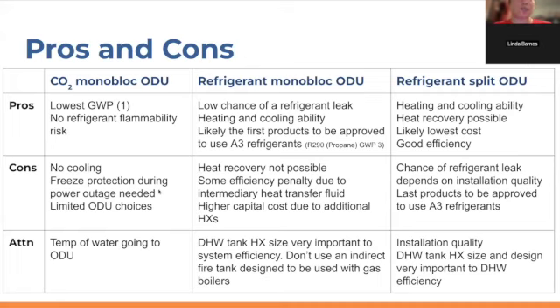Now, there are some efficiency penalties to having that water glycol intermediate working fluid and the additional heat exchange that needs to happen in order to switch heat transfer fluid. The efficiency penalty of that is generally quite small, but it depends on how well it's installed and the piping layout. If you have a spaghetti of water pipes, then you're going to have a non-trivial amount of efficiency penalty. But that's the same with refrigerant. If you have a spaghetti of refrigerant pipes, then your applied losses are kind of high.